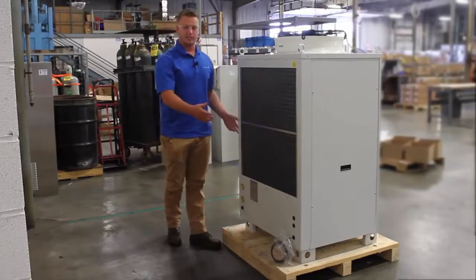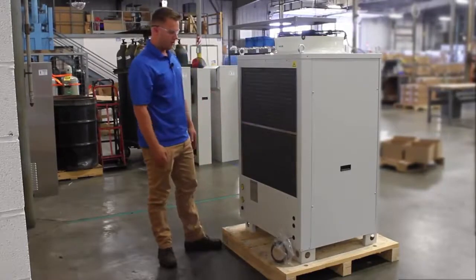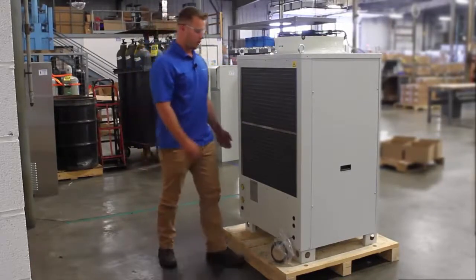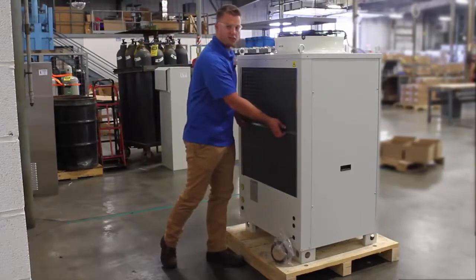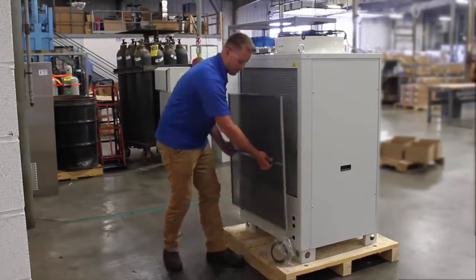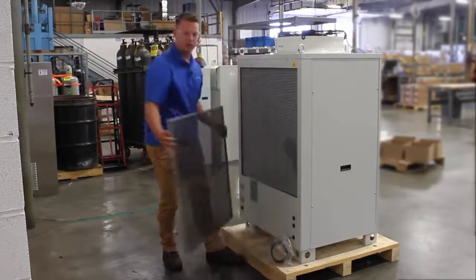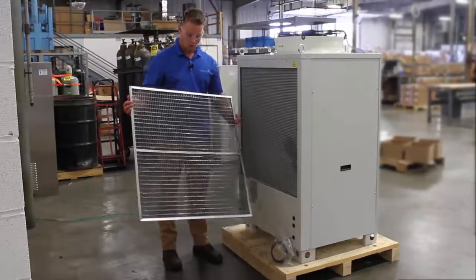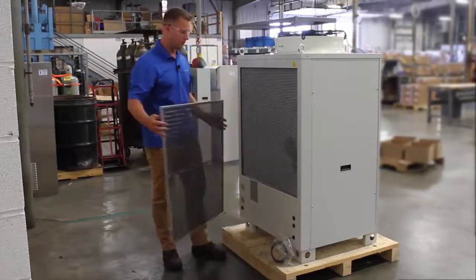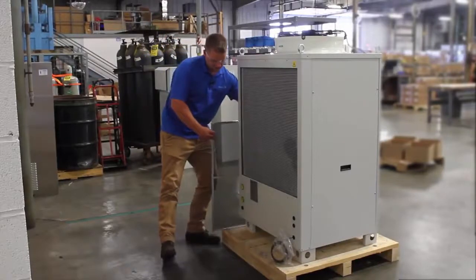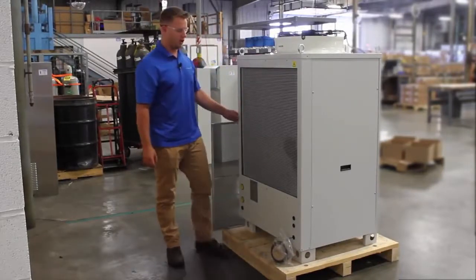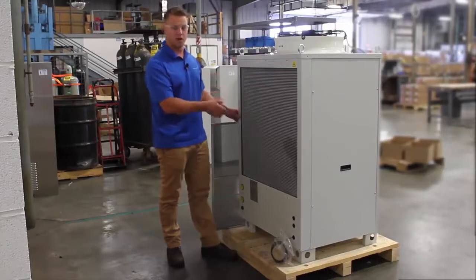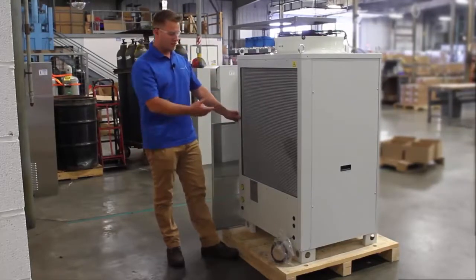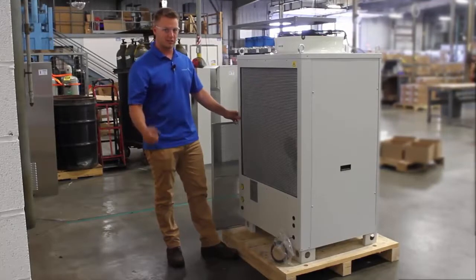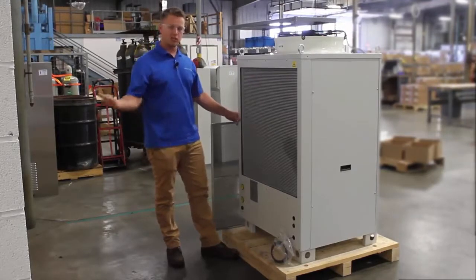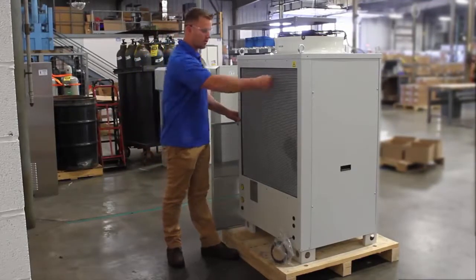The largest side of this chiller here is going to be your condenser coil. Right here we have a filter. The filter comes out very easily. That's all you need to do. This filter can then be washed or replaced based on how dirty it is. Inside here you'll see one of the key benefits to this chiller is it comes standard with a microchannel condenser. Some of the benefits to a microchannel are, number one, it's very easy to clean. If you have an extremely dusty environment, all you have to do is hose this out with compressed air.